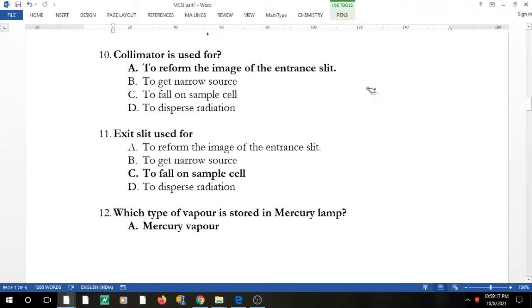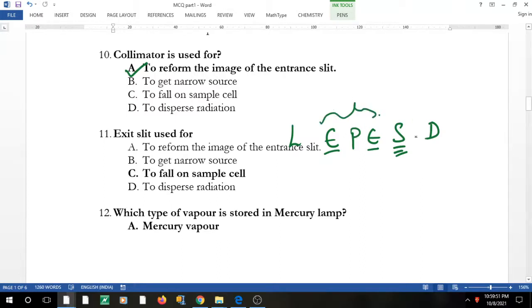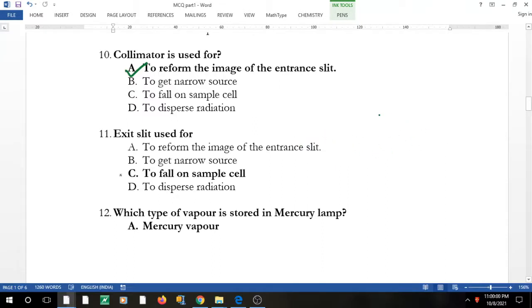The collimator is used to reform the image of the entrance slit — whatever light the entrance slit allows in, the collimator reforms that image. Question 11: the exit slit is used to allow the light to fall on the sample cell. Entry slit → prism/grating → exit slit → sample → detector. The exit slit selects only a single wavelength to fall on the sample.